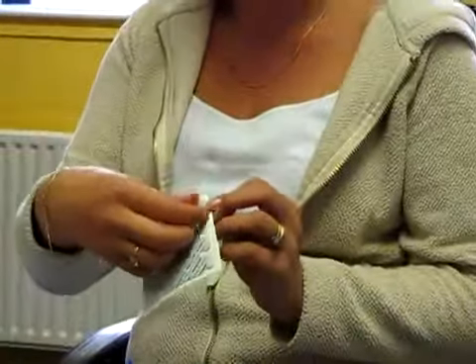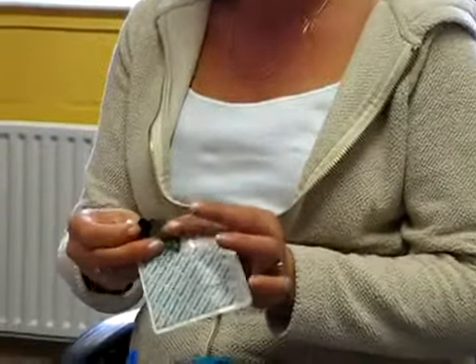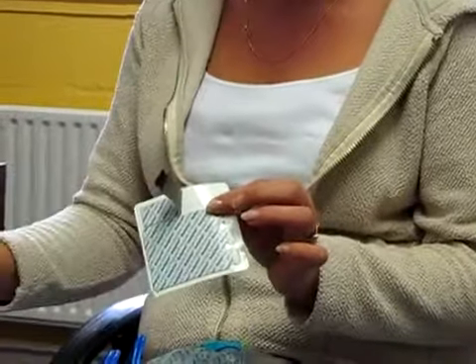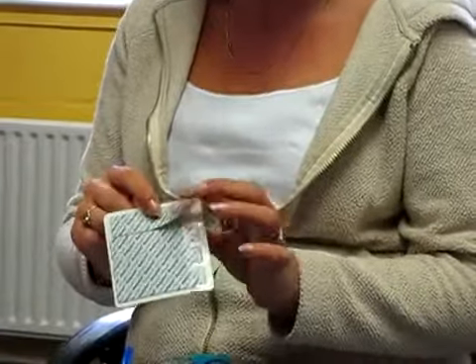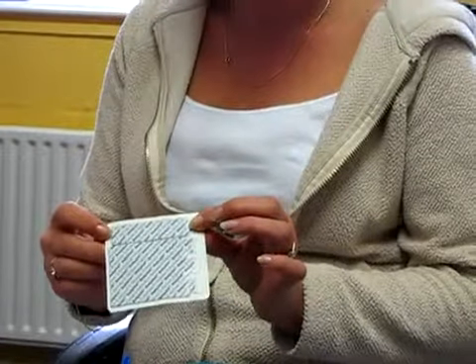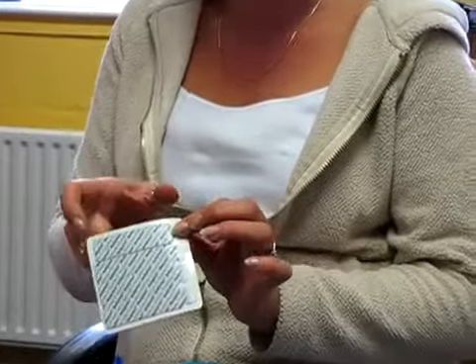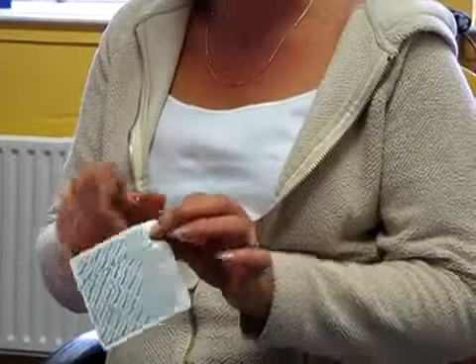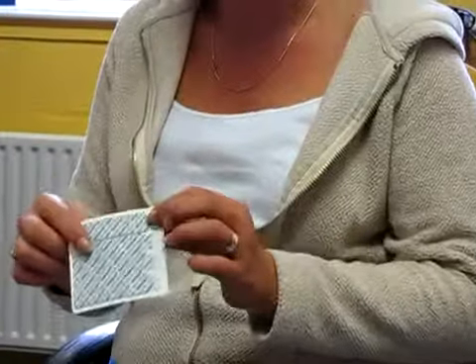Before I start on the device itself, I'll just show you a little bit about the electrodes. These have been especially designed for Bodystat devices. The gel on the inside is particularly sticky, and that's been calibrated for use in Bodystat devices. We do say that for the multi-frequency devices you need an extended surface area for the electrodes and a very good connection on the hands or the part of the body that you're using it for. So don't cut the electrodes in half, and do make sure you are using the larger electrodes.